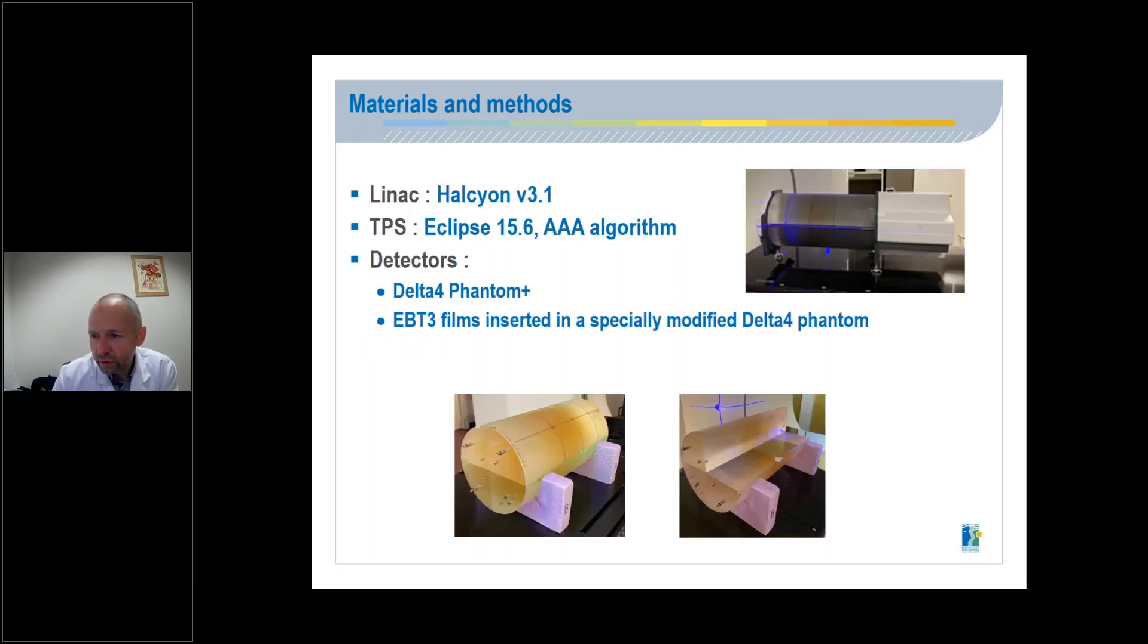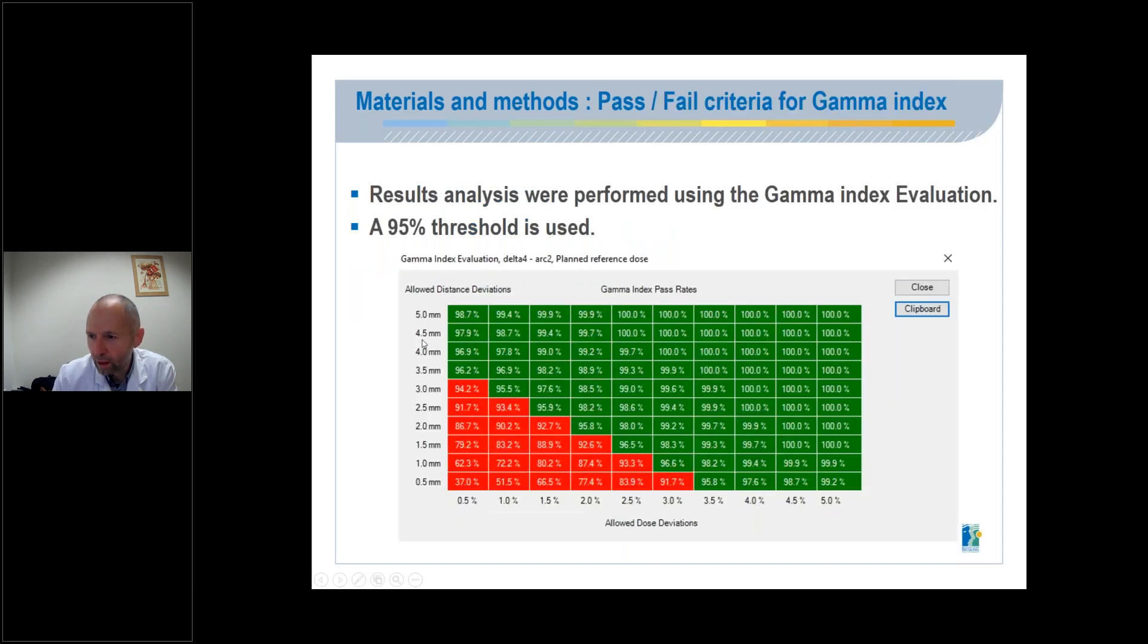The linac used was a Halcyon version 3.1. The TPS used was Eclipse version 15.6 with a triple A algorithm. And for detectors, we use a Delta IV Phantom Plus and an EBT-3 film inserted in a specially modified Delta IV Phantom. The results were analyzed using the gamma index evaluation. We use a 95% threshold.